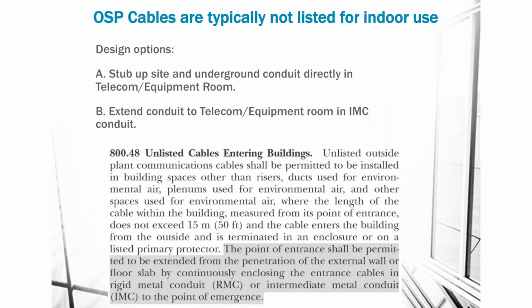The problem with OSP cables is that they're unlisted for routing inside a building. So you have a plenum space, that's your area above your drop ceiling but below the structure, that is used for return air. Then any cabling in there needs to be plenum rated. So that's our main design parameter.